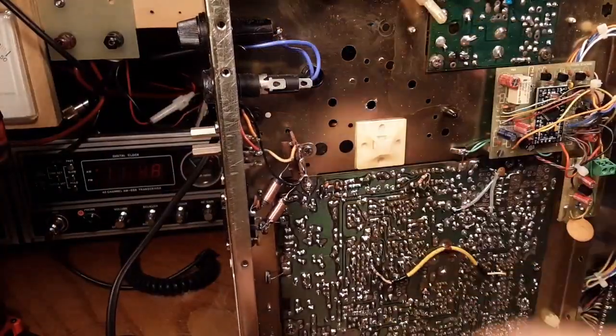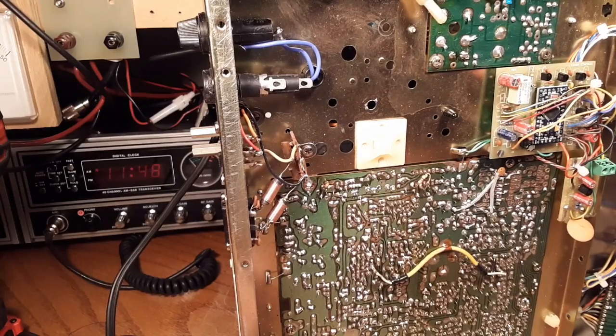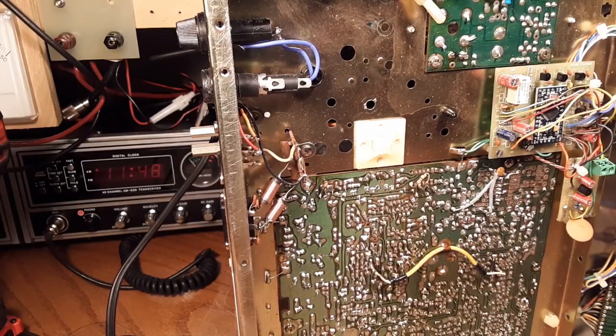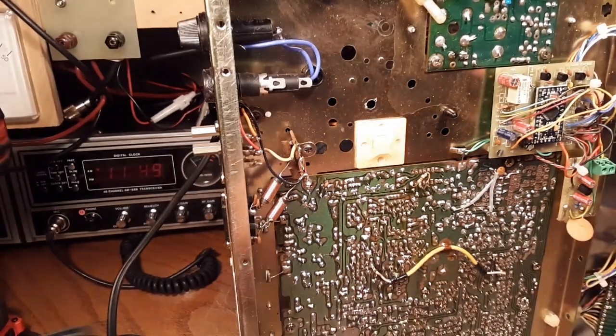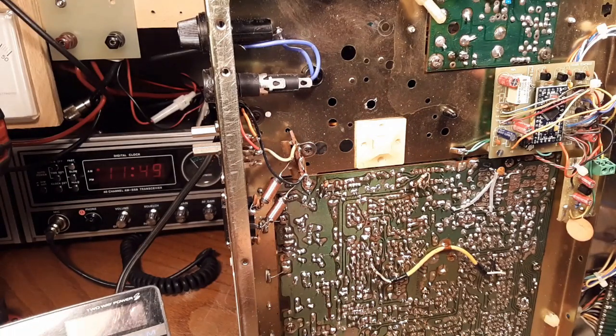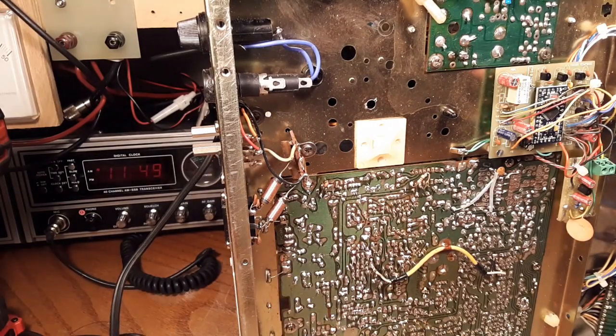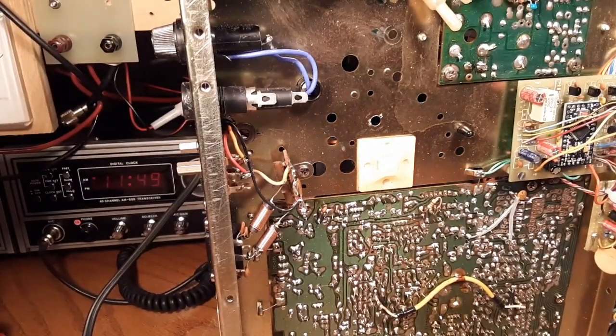So that'll get me my line fused at 1 amp, good for 125 watts. If the transformer's 60% efficient, that means if you're drawing roughly around 75 watts out of the secondary, you might be kind of tweaking that fuse a little bit. I don't think it will ever blow, but if it does, I could put a 1.25 or 1.5 amp in there, but no higher than that.